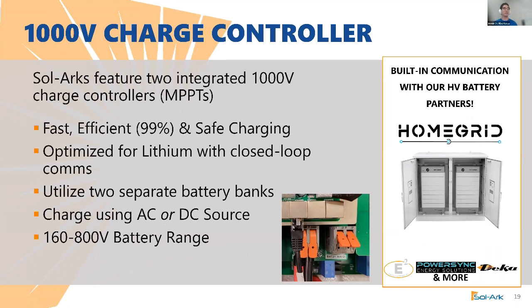So for the 60K, we do have two integrated 1000 volt charge controllers for fast, efficient, and safe charging as well. For the 60K, it's also only closed loop communications with lithium batteries, and you still can use up to 2 different battery banks per system. And since you can parallel up to 12 units, each unit will need its own battery bank as well. So you can charge using AC or DC source, as I've mentioned, and the difference on this one is the range of the voltage for the battery. The battery voltage range is 160 volts up to 800 volts for the 60K. And so we do have built-in communications with our high voltage battery partners, and HomeGrid specifically always stands out.